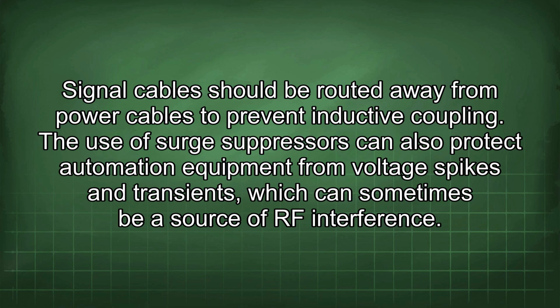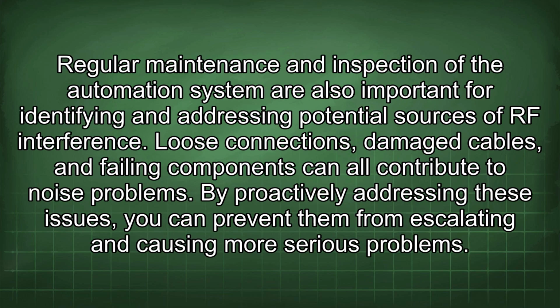Regular maintenance and inspection of the automation system are also important for identifying and addressing potential sources of RF interference. Loose connections, damaged cables, and failing components can all contribute to noise problems. By proactively addressing these issues, you can prevent them from escalating and causing more serious problems.